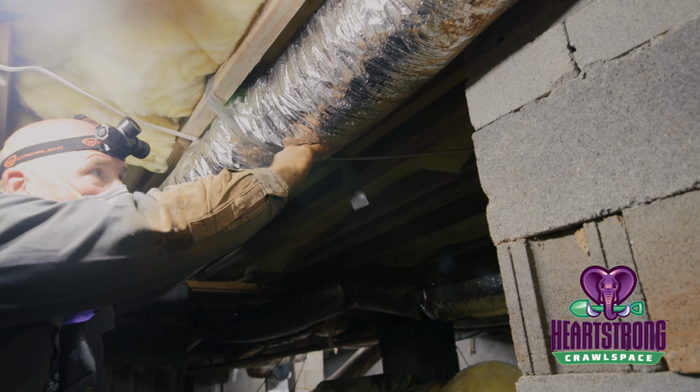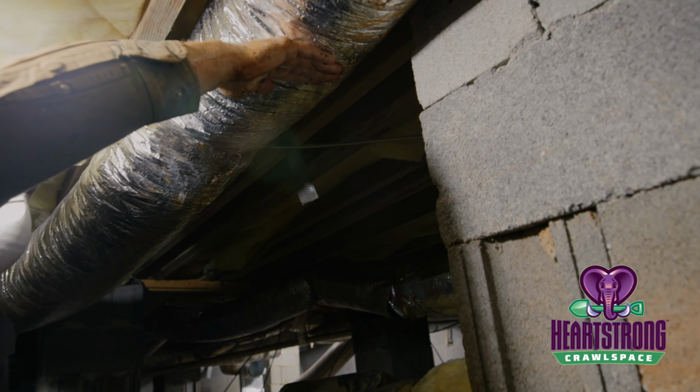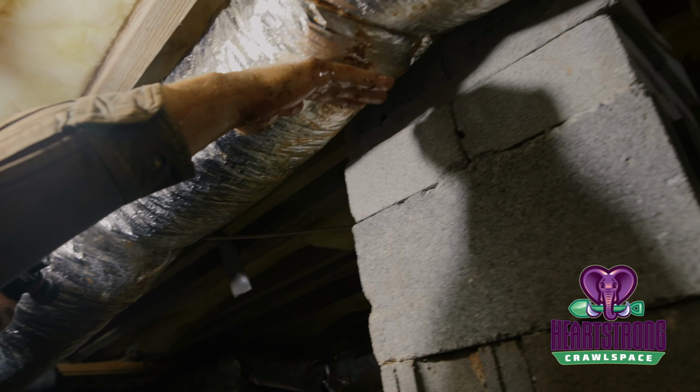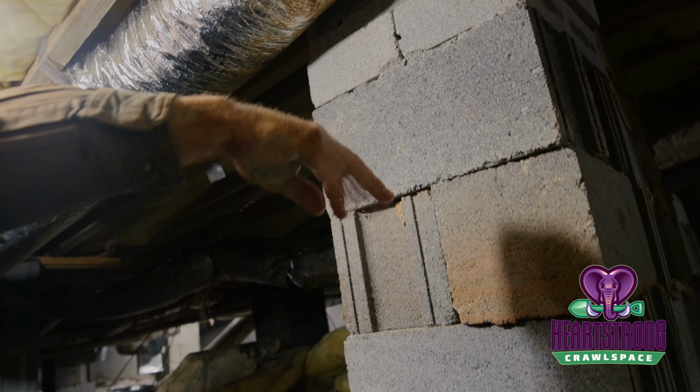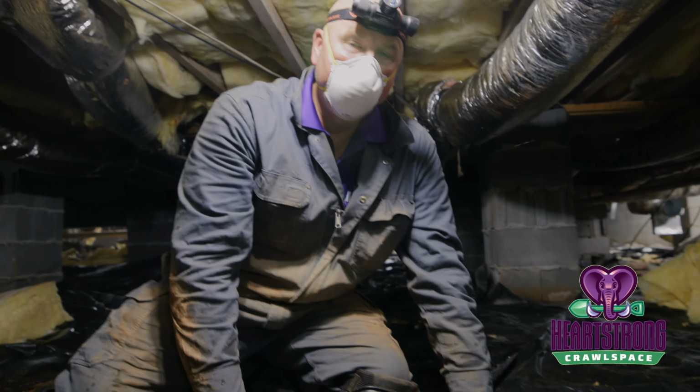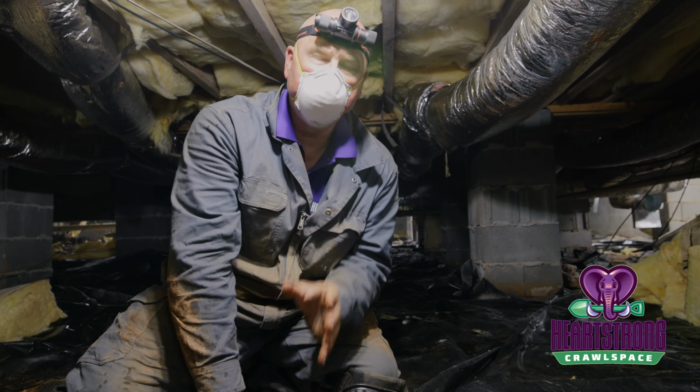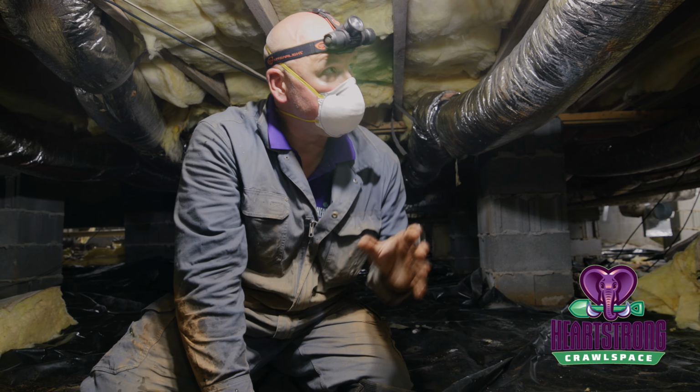If we look up here real quick, this is the source of the water. It's actually coming from the HVAC ductwork. It's literally raining off of the ductwork into this crawl space. And that's because of the air exchange.